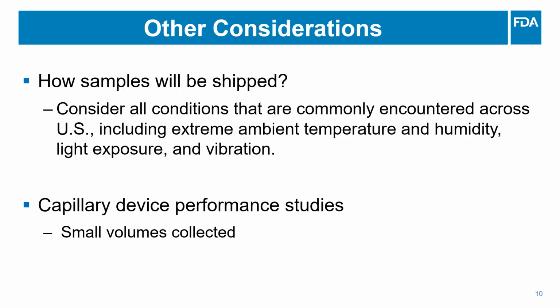Another challenge during validation of capillary samples is that the volume is too small for testing all the analytes that the device is intended for. This may require collecting multiple samples while accounting for potential biological differences in analyte hemodynamics, or enrolling additional patients to collect sufficient data. We acknowledge that the difficulties to generate the data to support safe and effective use of these devices are not trivial. But if the ecosystem has the right stakeholders finding solutions, it is possible to see progress in the near future.